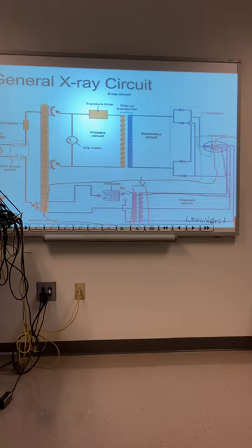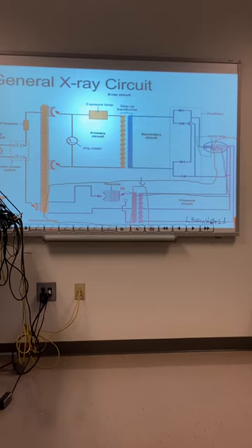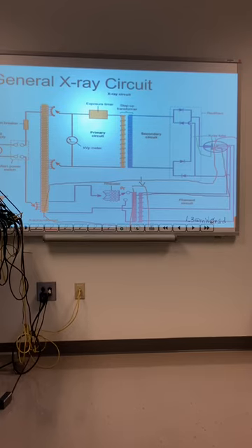So you said it goes through the rheostat, the exposure timer, then the anode, and then it goes back through it again. Primary. Secondary. Anode side of the tube. The anode side sends it to the cathode, but when it gets in the cathode, it goes to rheostat, exposure timer, step down, and then out. Okay, that's helpful. I was wondering how the filament happens. Remember, the anode side of the tube is on secondary. The filament side, which is part of the cathode, is on the filament current.